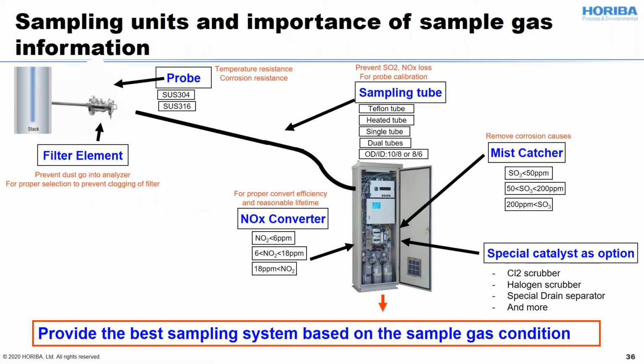All right, and this is the system overview. We carefully choose the right parts for your applications. Sampling probe with filter, and depending on your application, the material may change. We consider the configuration and material of sampling tubes. Depending on the NO2 concentration in your sample, we provide a bigger NOx converter, right here. And depending on the SO3 concentration, we pick the suitable size of the mist catcher. Also, other options like the halogen scrubber and Cl2 scrubber are picked, and a different design of drain separator, etc. It is our job to propose the best sampling system for your analyzers.